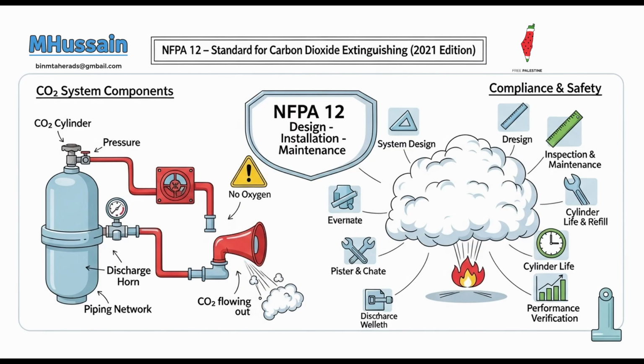It's explicitly stated that a mere electrical service disconnect switch is not a substitute for a physical lockout valve. Right, because the CO2 has its own pressure. As the CO2 system operates under its own pressure independent of electrical power. This highlights the multi-layered approach to safety. That makes perfect sense. It's about making absolutely sure that while the system protects against fire, it doesn't inadvertently harm the very people it's designed to protect.